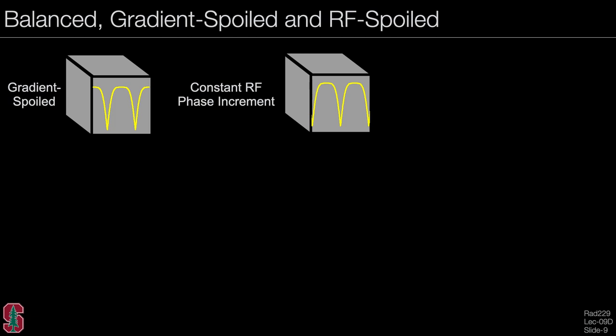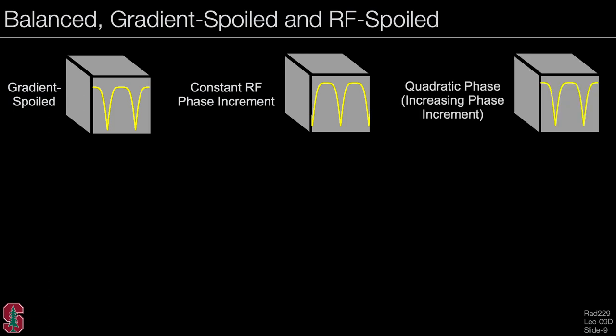Putting this together with balanced SSFP, gradient spoiling, and RF spoiling: in a gradient echo sequence, we take the balanced SSFP signal and compress it into a voxel. A constant RF phase increment shifts this profile, just like shifting the center frequency of the scan. A quadratic phase increment is actually increasing this phase increment linearly over time, so the profile is shifting through the voxel.